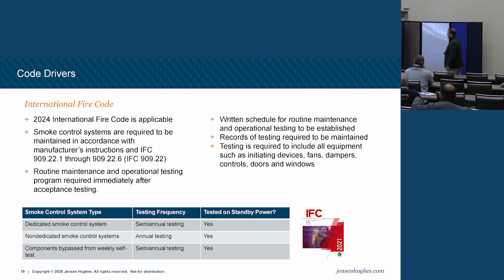Components bypassed from the weekly self-test, I have to test semi-annually. So if I'm bypassing them during a weekly, these systems, as part of the UUKL, they weekly look at all the actuators and they test it and they generate a report. If I have to bypass those because the main door's too busy, I can't do that one, then I have to test those specifically on a semi-annual basis. Does that make sense? Kind of blowing through that.